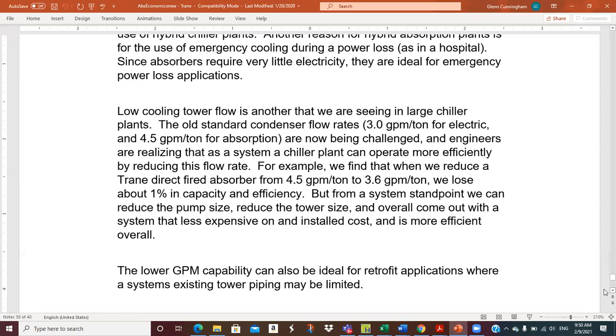A 1,000-ton chiller used to be 3,000 GPM. Now it might be 2,500, 2,400 GPM, at least during parts of the year. And remember, we need more cooling tower capacity for the absorption chiller, right? Because we have the absorber, which is generating heat. That's an exothermic reaction. And then we have the condenser.